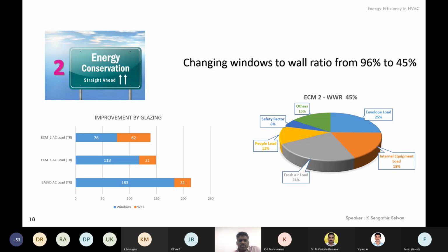But if you see overall, we have around 138 TR, which is still much better than your earlier 215 TR. So around 100 TR we have reduced now by changing the window wall ratio from 96 to 45% and changing single glaze to double glaze.